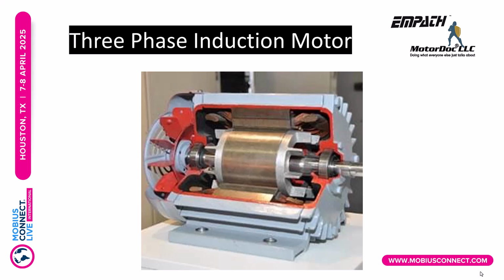Matter of fact, what's kind of interesting about that, because we've heard some new technologies out there, is that's actually a Faraday cage. The magnetic fields are trapped within that machine. Now you can get some leakage to the surface, and that's usually what people think that when they think they're detecting stray flux, they're actually detecting stray currents on the surface of the machine, which is ground noise, leakage from the machine, and other conditions.